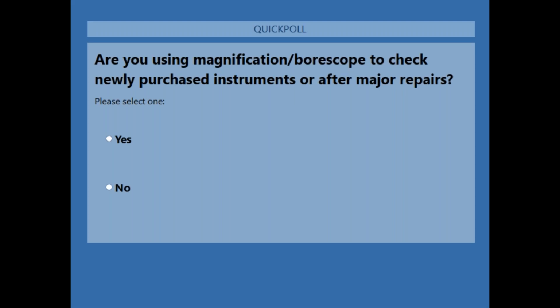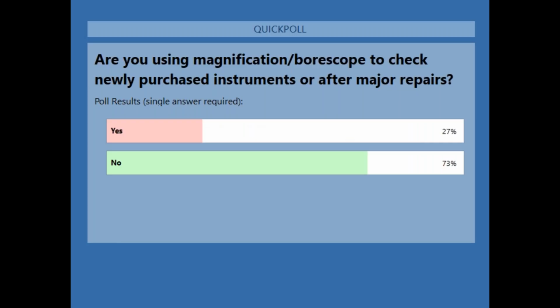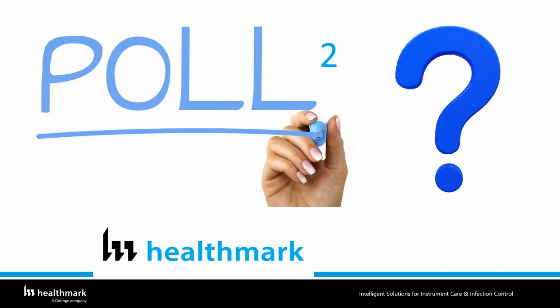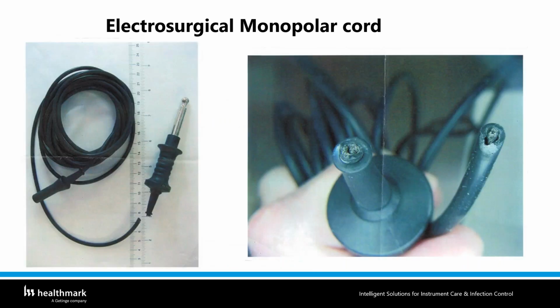And on this one, we found out that as a biomed, we always do the incoming inspection to see if they meet all the requirements. But in this portion of them, an endoscope is $35,000, $40,000 a piece, so when you receive them or when they come back from repair, do they really do what they're supposed to do? So I don't know, Linda, if you got the answer. Yep, I'm going to close that and share it. You have yes, 27%, and no, 73%. Okay.